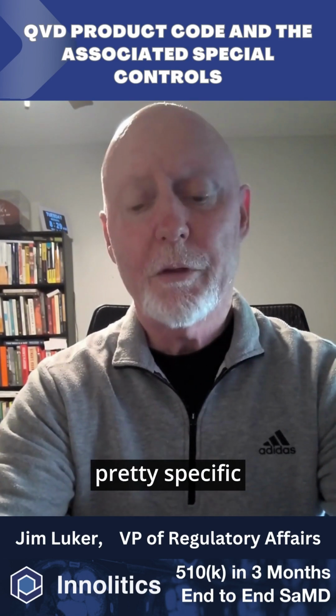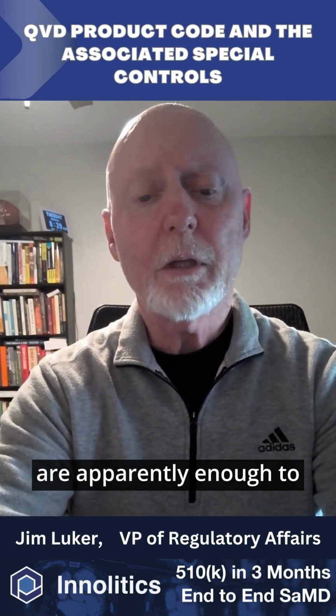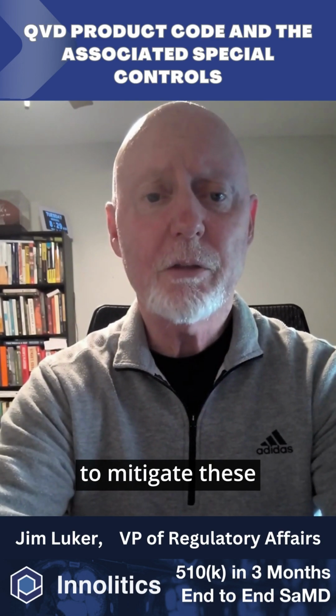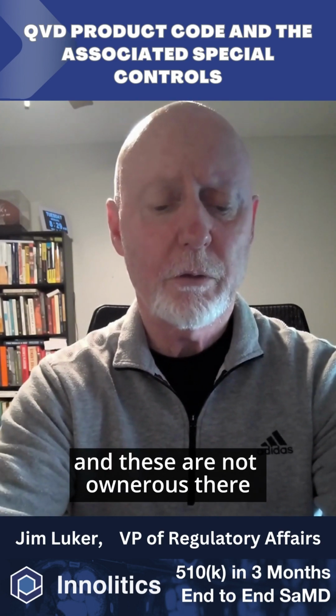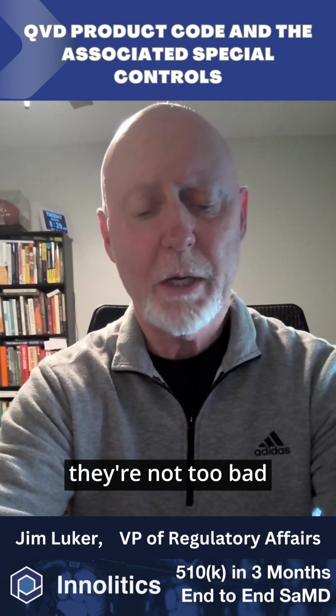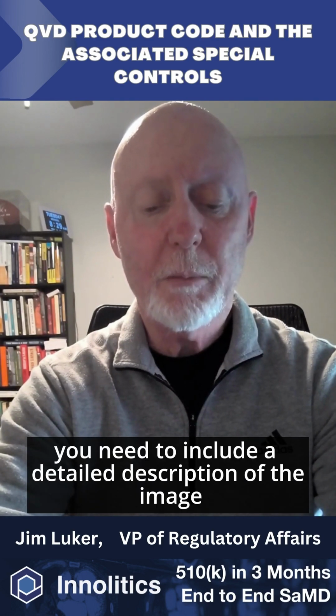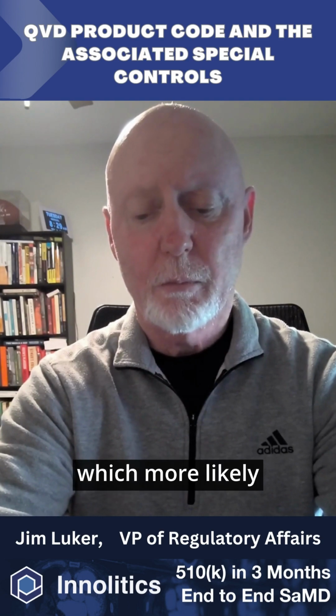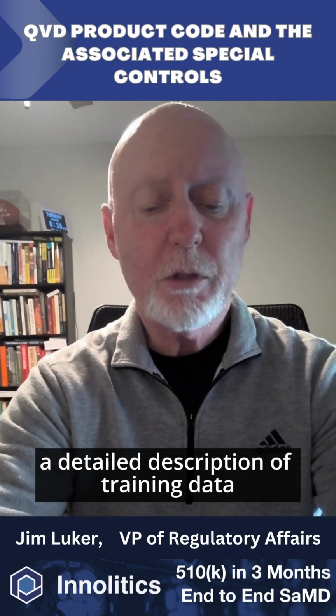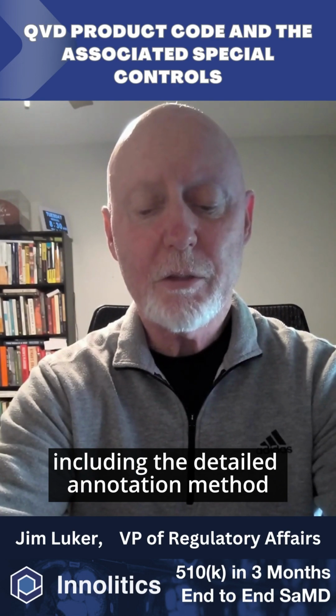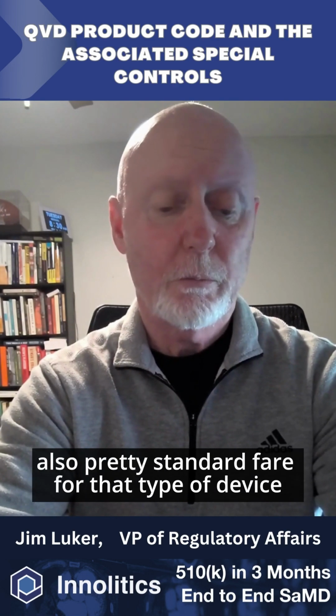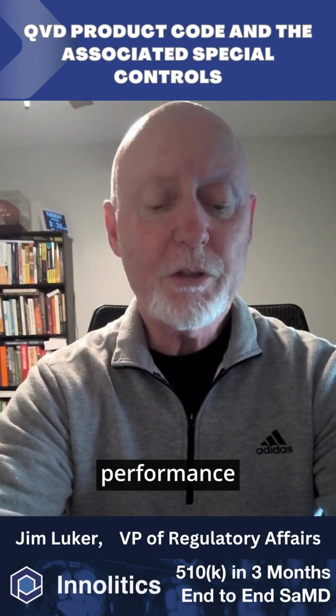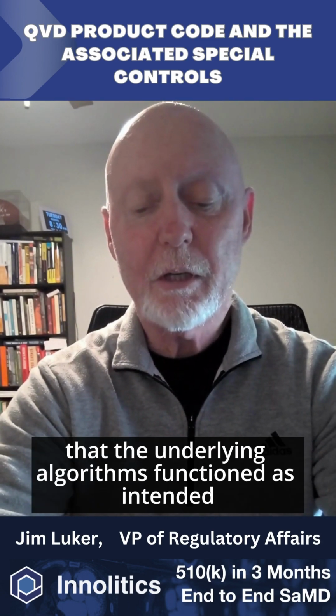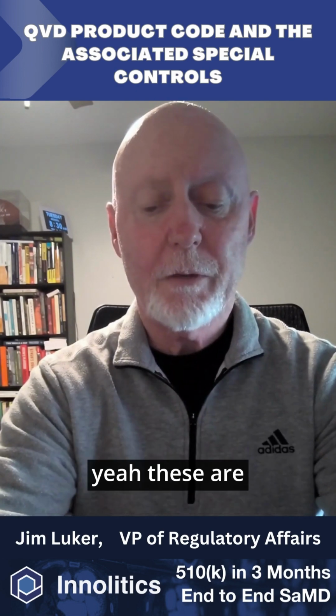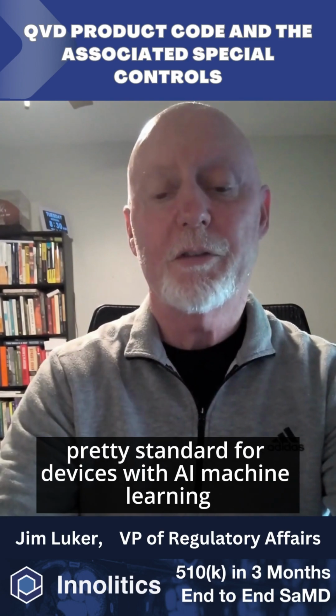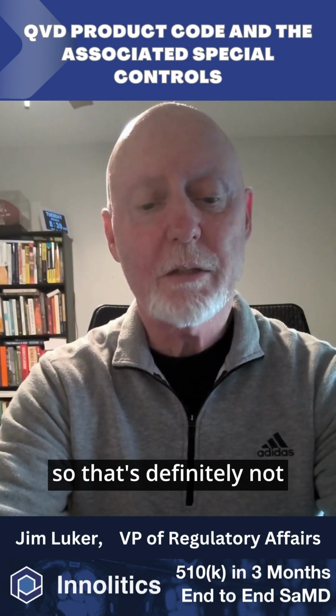That's again pretty specific. The special controls themselves are apparently enough to mitigate these risks, and these are not onerous. There's really just a few, and they're not too bad. You need to include a detailed description of the image post-processing algorithms, which more than likely you would do anyway. A detailed description of training data, including the detailed annotation method and important cohorts that were used. Also pretty standard fare for that type of device. Performance testing protocols and results that demonstrate that the underlying algorithms function as intended. Yeah, these are pretty standard for devices with AI machine learning. So that's definitely not too bad.